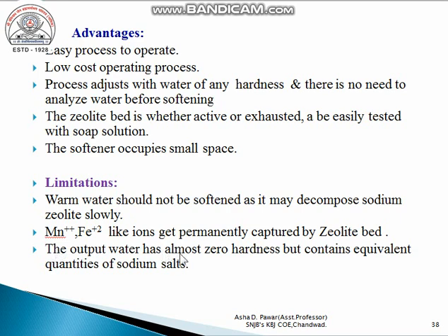The output water has almost zero hardness but contains an equivalent quantity of sodium salt. With the help of sodium zeolite, if we convert hard water into soft water, the hardness-causing impurities are removed. Water has zero hardness but contains an equivalent amount of sodium salt. So it's a very important process for water softening.